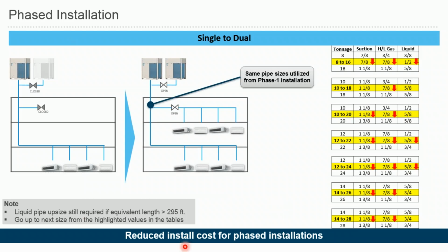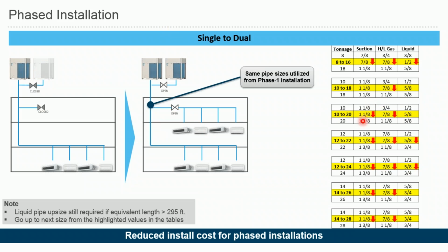If you look at this slide, switching from single module to dual module, you will have a certain pipe size configuration, pipe size guidelines, which will be provided in our engineering manuals. So you start with the single module over here on the left side. For future condensing unit addition, you put that valve there and close it, and you install your first indoor units for the first phase of your project. If another tenant moves into that building a year later or whenever it is, you again leave another isolation valve there and close that one as well. So you don't have to install all your indoor units at the same time at the initial stage of the project.